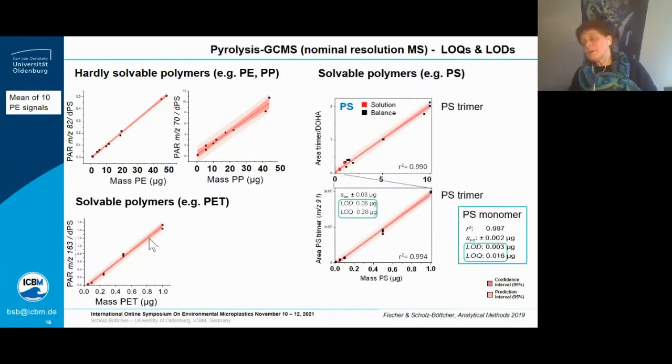And for this determination of detection limits and quantification limits, two methods are common. One is only taking the signal-to-noise ratio. We will show that later. And there you say the detection limit usually is a signal-to-noise ratio of a data point that has a signal at least 3 times higher. And for quantification, it has to be 10 times higher. You can also use a calibration curve-based method, which includes also analytical variations, which are also there.